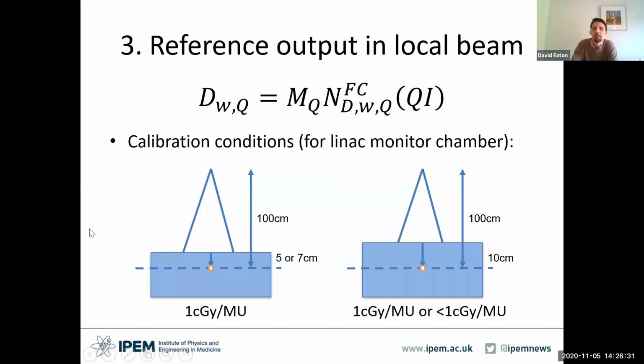So finally, once we have the calibration coefficient for our field chamber, we can use that to measure a reference output in our local beam. And again, that simply gives us the dose to water in that particular beam quality: the measurement corrected for influence quantities for that particular chamber and setup, multiplied by the calibration coefficient, this time for our field chamber, giving dose to water in a beam quality with a certain beam quality index.